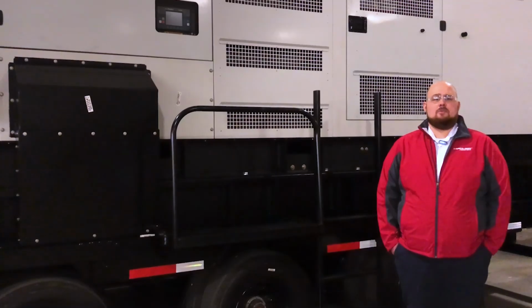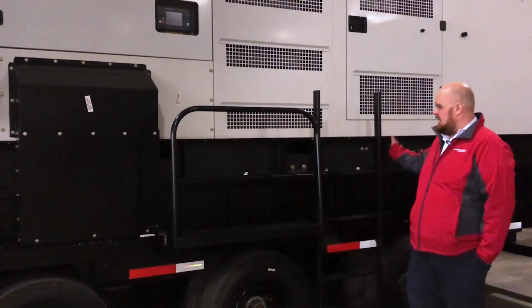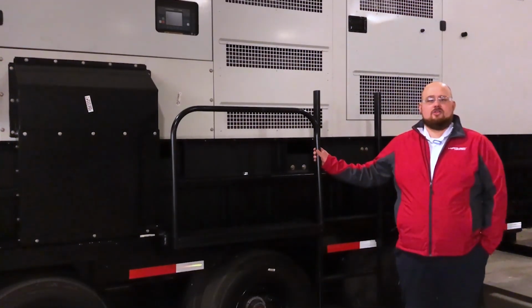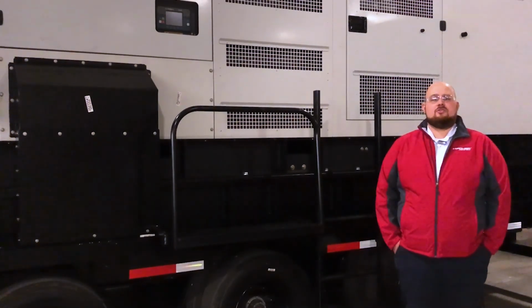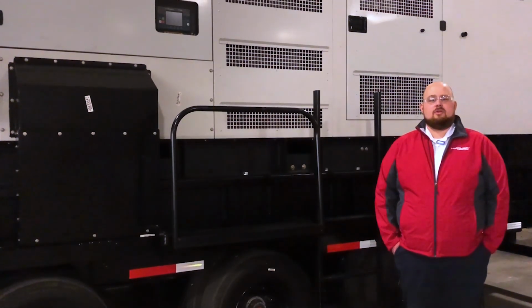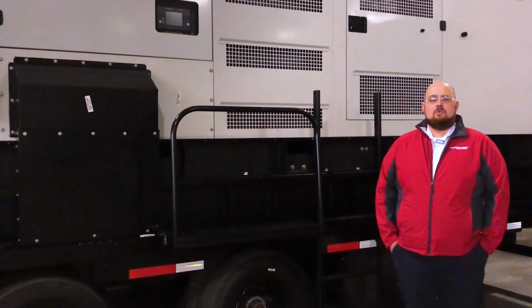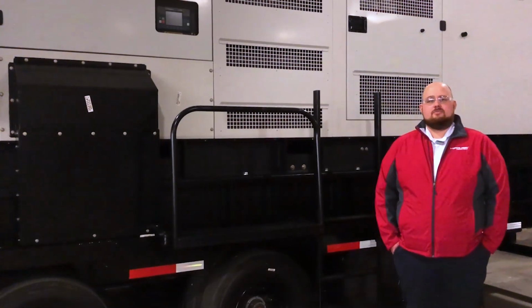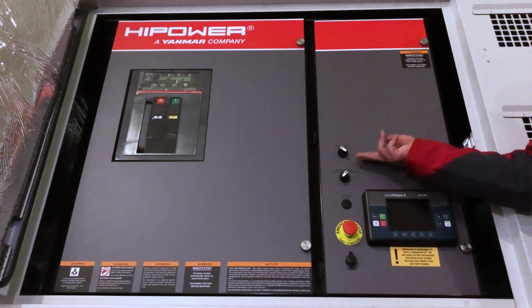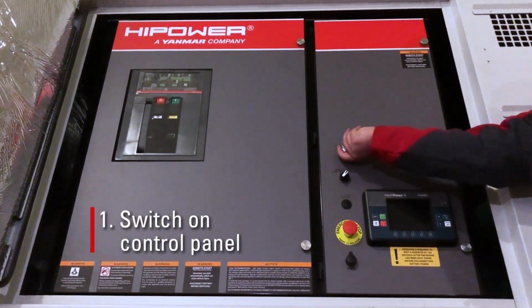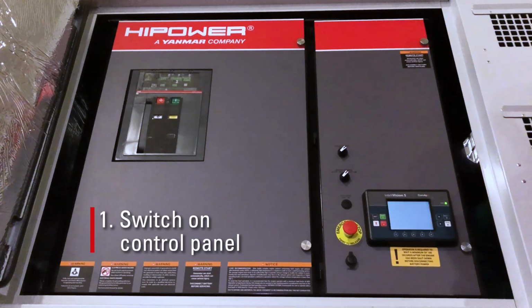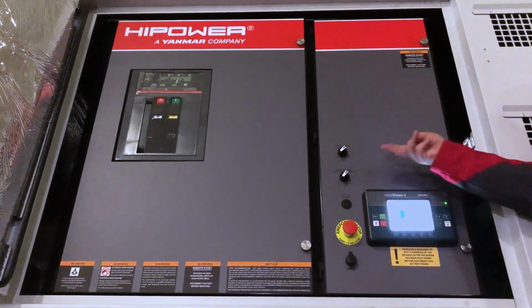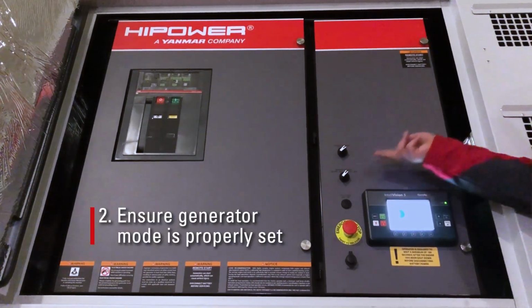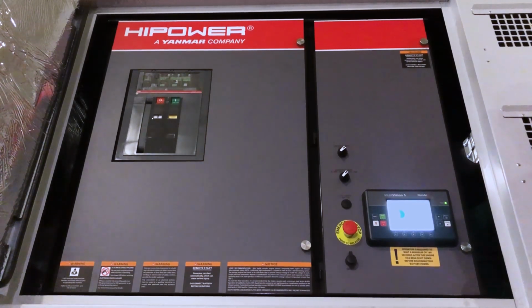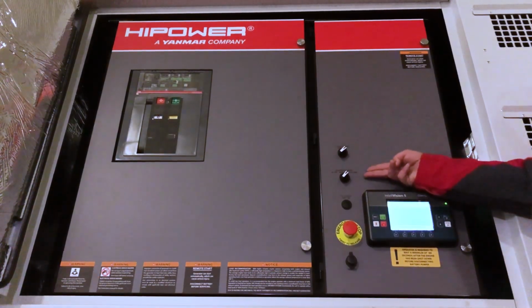Before you begin your power-up sequence, please ensure that your ladder and your handrail are properly positioned, if so equipped, and please ensure you're wearing your personal protective equipment required by your specific location or branch. Now we will begin the first step of the power-up sequence. The first step of the startup sequence is to turn on the control panel. Once the controller boots up, ensure the generator mode selection switch is in the correct position for your application. For a standard twin pack, you want to ensure that both generators are in line.